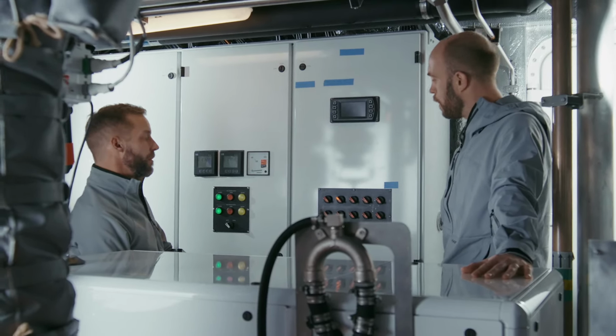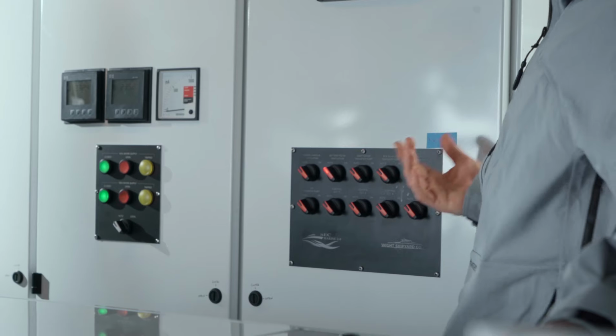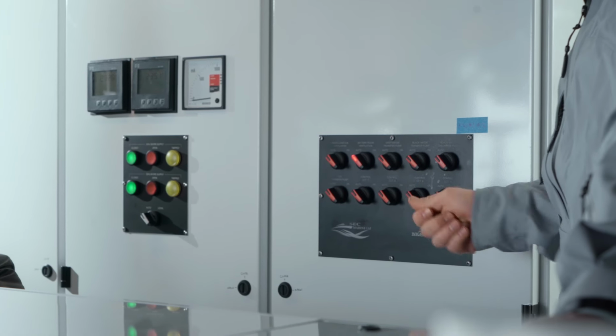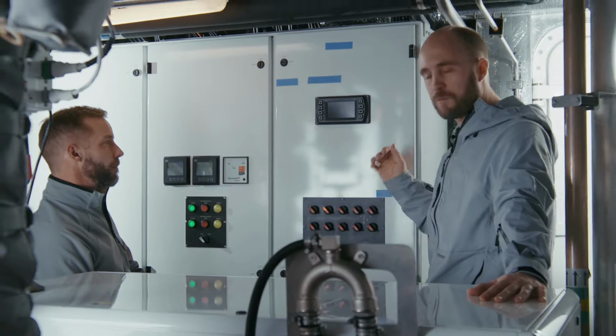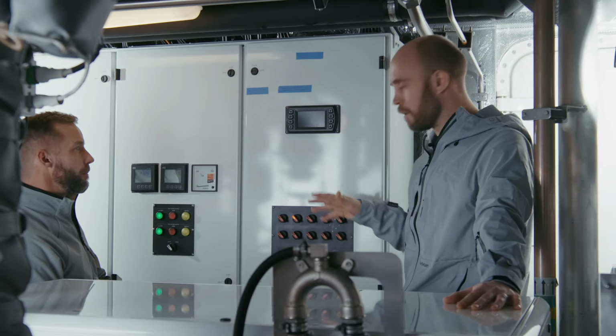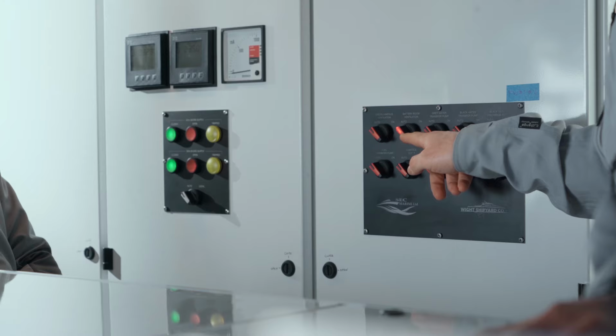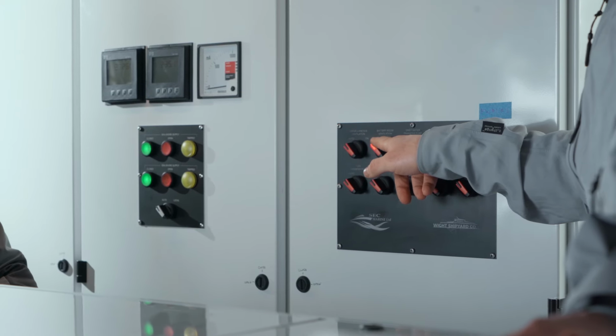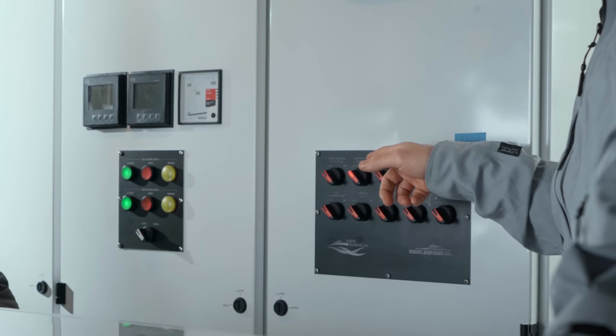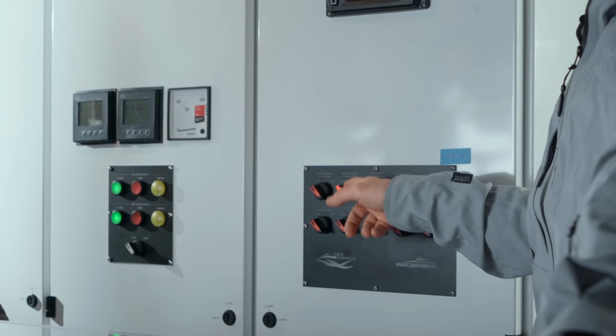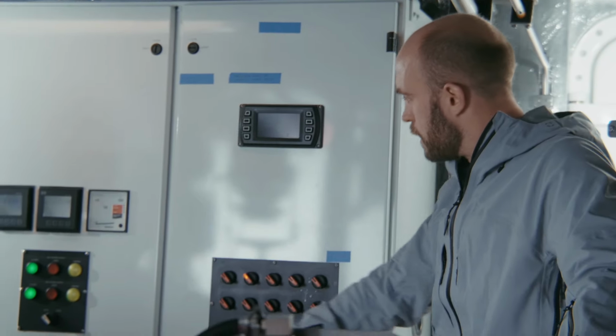Yeah, as an example, you can see here that you've got a number of switches which either have an auto or an on mode. On mode means I'm turning that thing on, so that pump will run. Auto mode means it's in control of the digital system. As an example, here we have one switch illuminated, for the battery ventilation, which shows that's on, being controlled by the digital switching system. That's why that's illuminated. You've got a similar looking panel down here for the DC side of things.